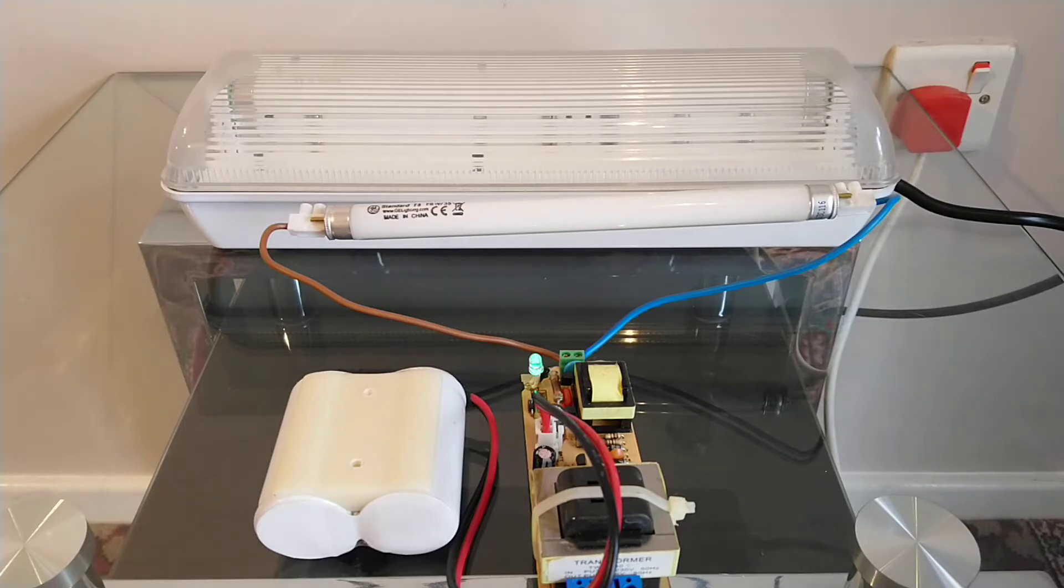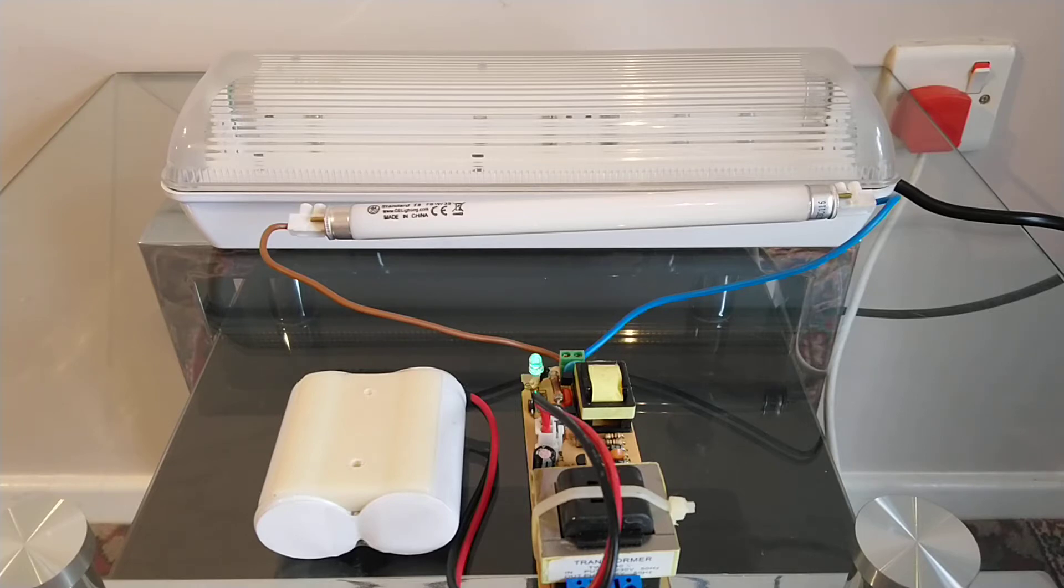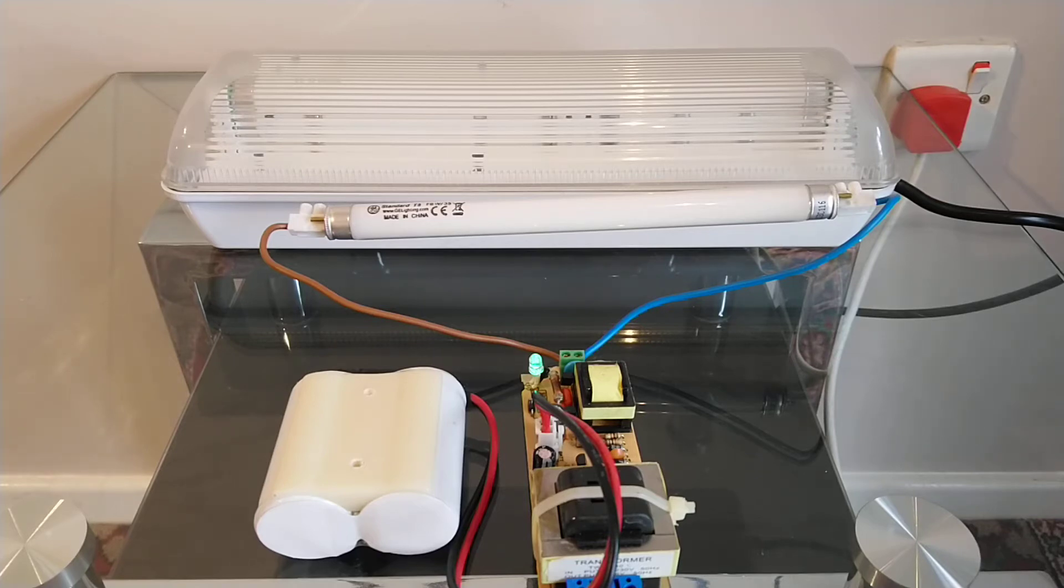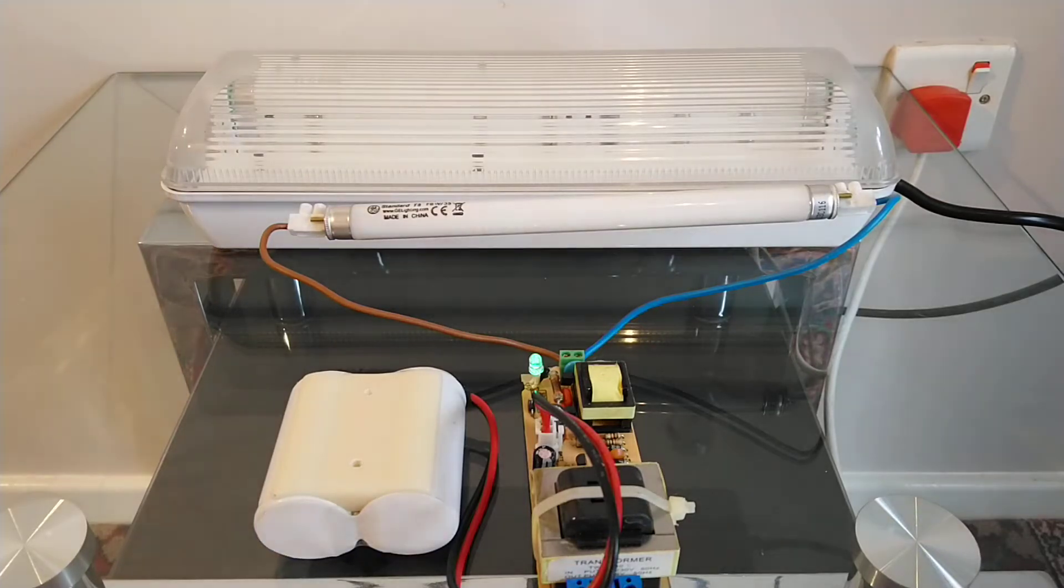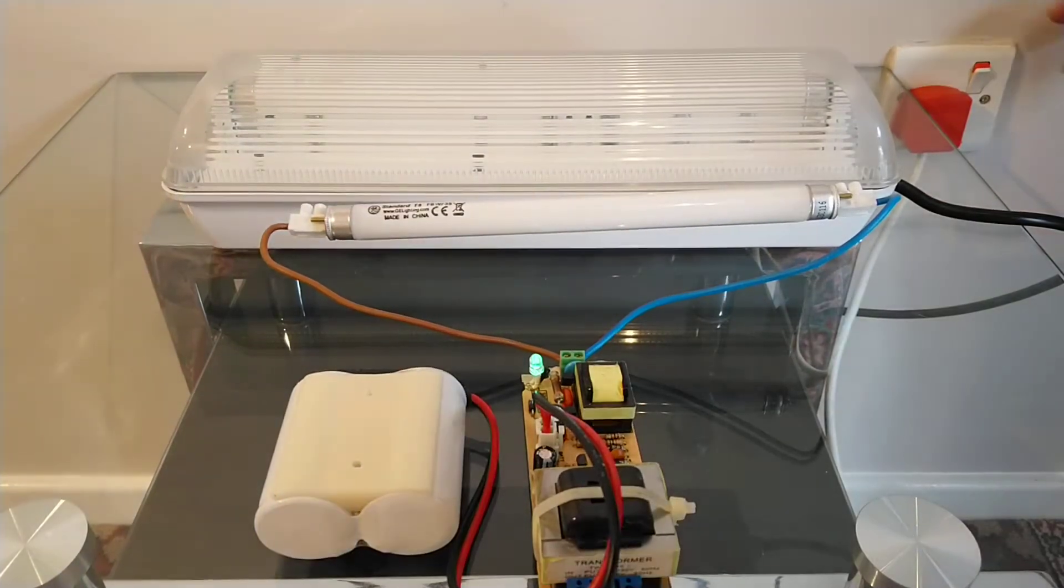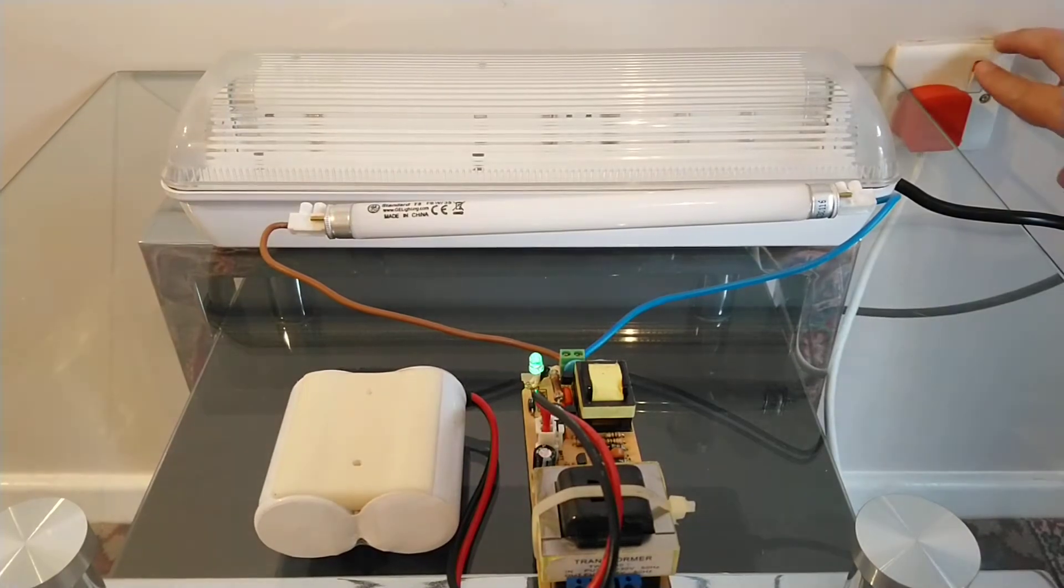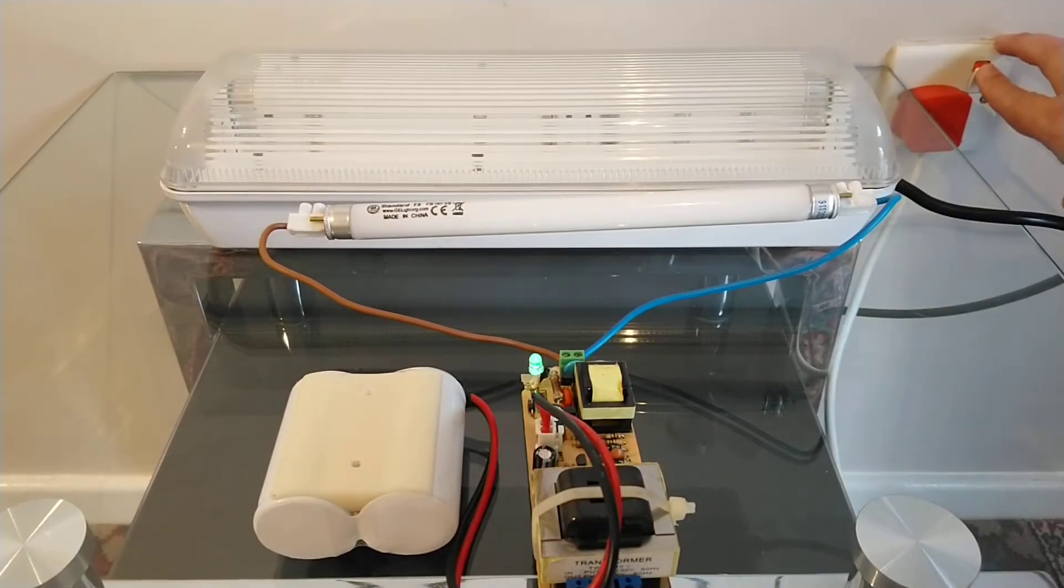So first we'll start with the emergency light. At the moment it's running 240 mains and is live, so I don't recommend touching it. So I want to turn it off first. Green LED will go out and the little fluorescent tube will come on.